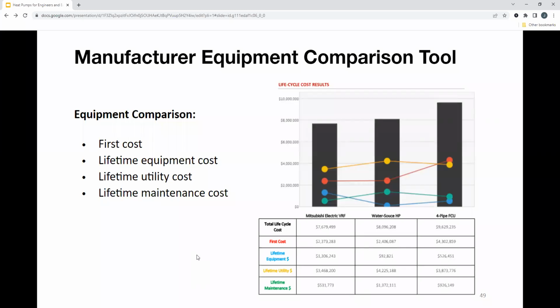And lifetime maintenance is the smallest cost because there's little to no maintenance that needs to be required. Indoor units just need to clean out your filters, check your condensate drains, all that. Condensing units basically just need to be wiped down with water, and clear any debris that could be stuck in there. That's about it. But yeah, this is a great tool. A lot of manufacturers do have access to this. So if you are looking to compare equipment, this would be a good option.